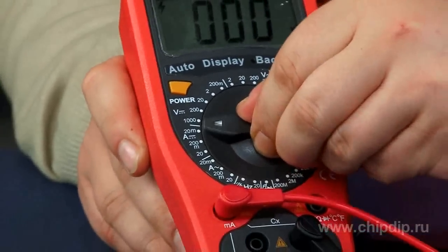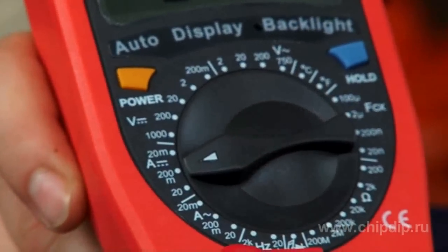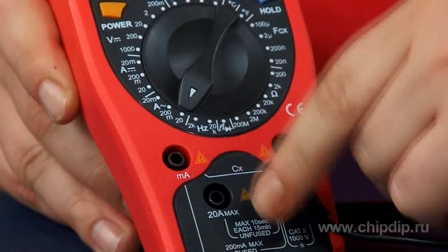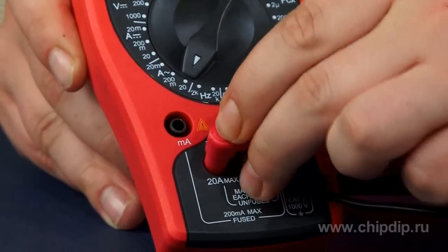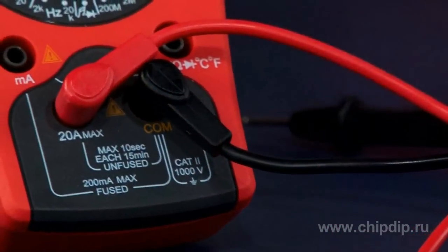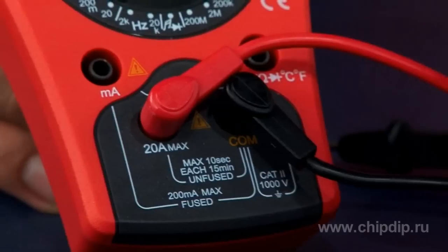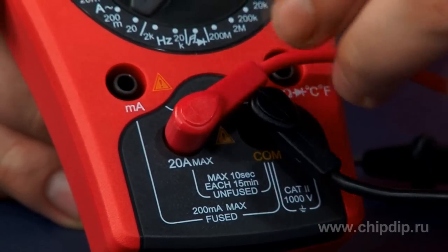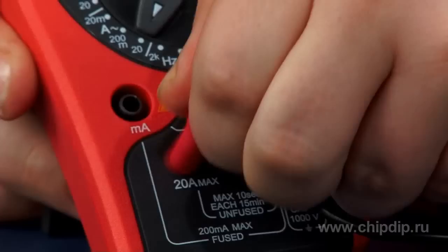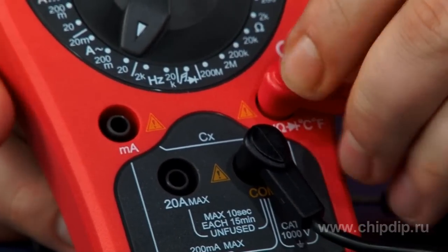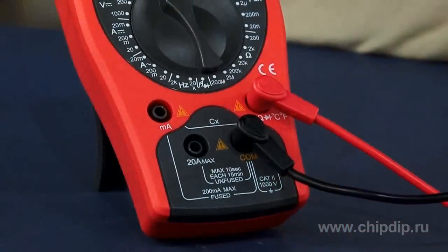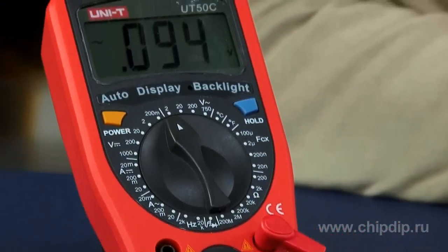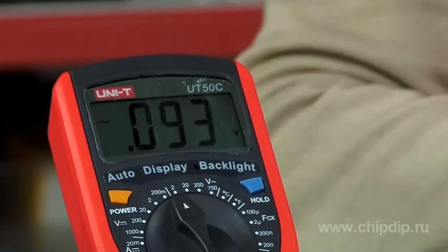Note that in order to measure current, connect the red probe to one of the two slots. If the measures are to be taken within the maximum range of up to 20 amperes, the probe must be connected to the lower left slot. The black probe is permanently connected to the COM slot, and the probe measuring resistance, frequency and capacity is to be connected to the upper right slot, as we may see.